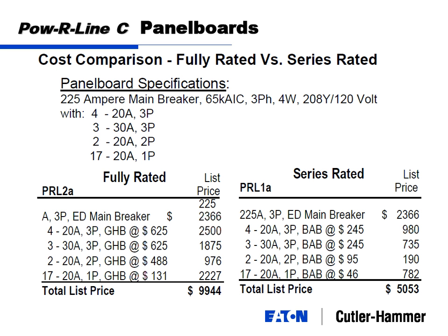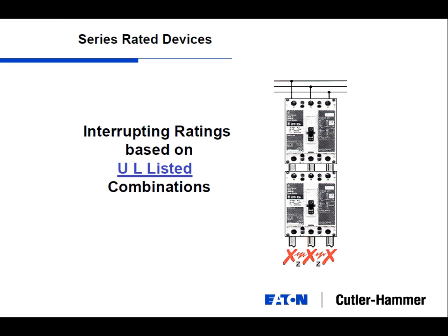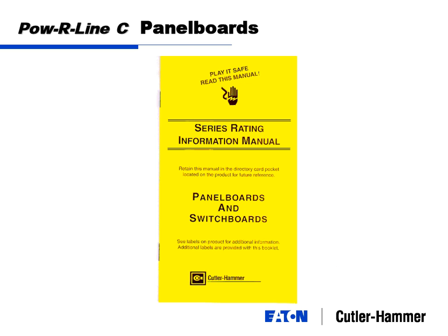Now, I'll give you, this is what they call a very good example. So you're not always going to be half the price to go series rated, but you know, it's good to note it's always something to look at, to keep in mind if it's acceptable to the engineer and if cost is a consideration. If you use these combinations, and if you do replacement, you must stick with the same setup, correct? Yep, as my setup man says, these are UL listed combinations, and this book comes in every panel board. So if you have a series rated panel board, that panel board will be labeled as series rated, and this book or something similar from our other guys will list the feeder breakers that are acceptable to be put in.